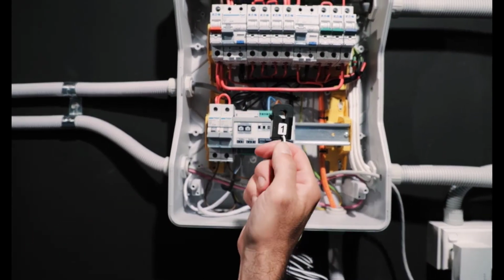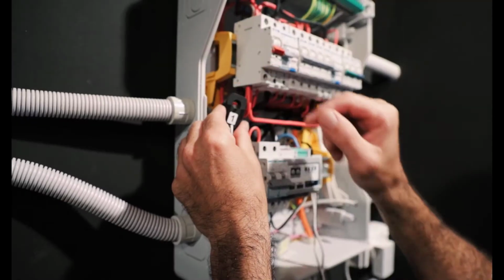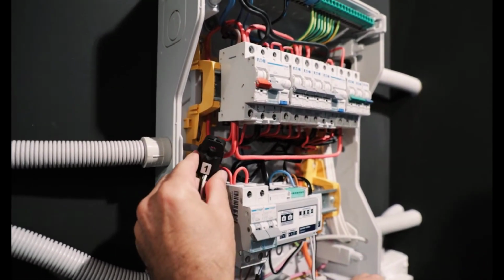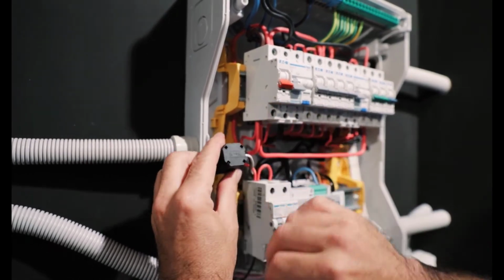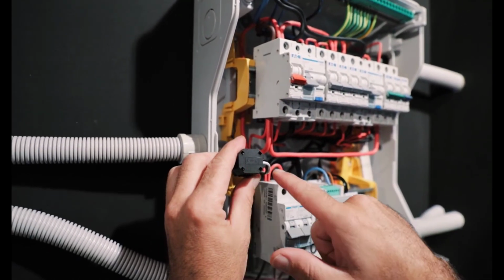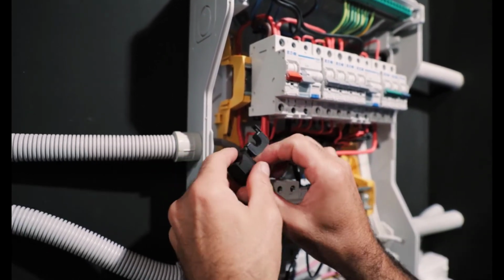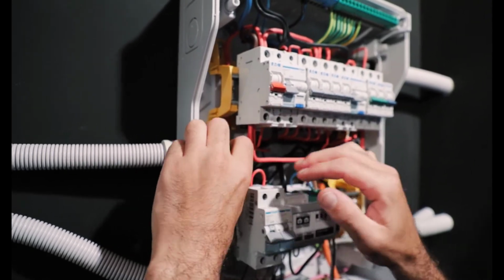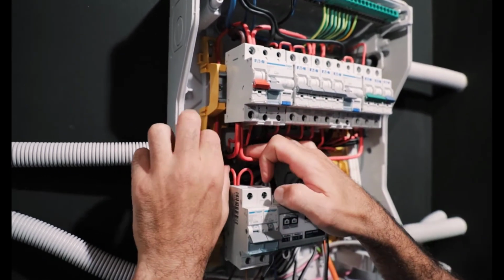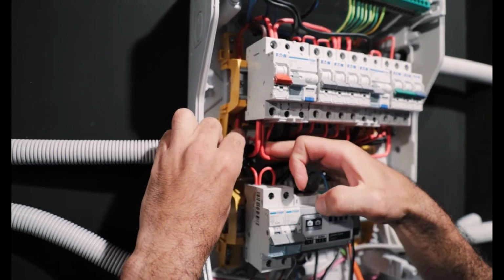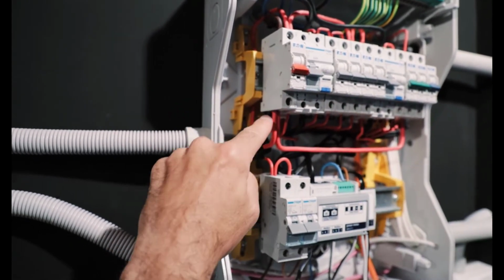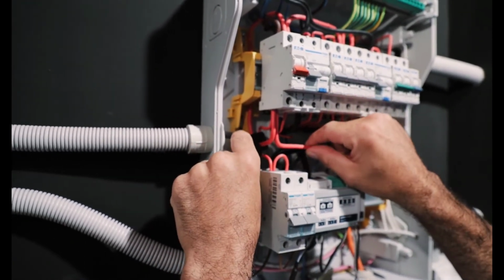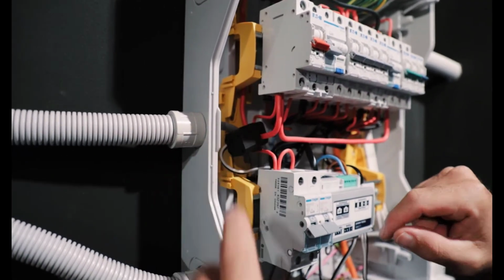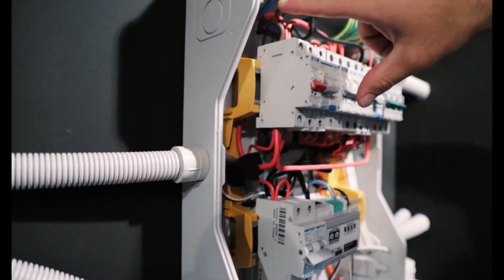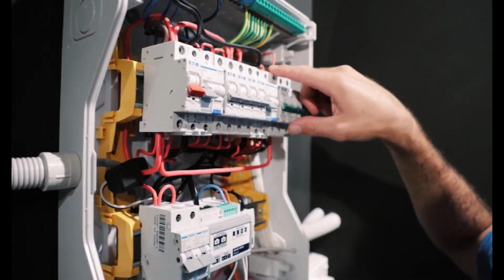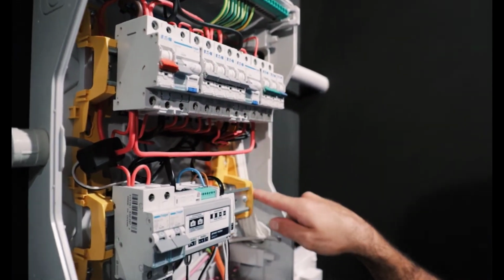As per before, we take CT number 1 and we just take that onto the supply coming out the main isolator, which is just going to the loads. So we've been able to separate out here just the load consumption itself. So all that power goes out through the MCBs, out to all the load circuits.